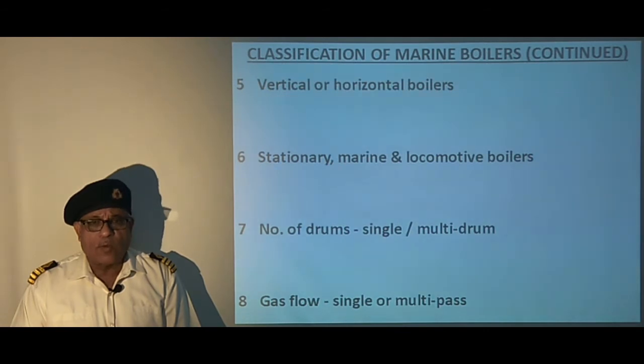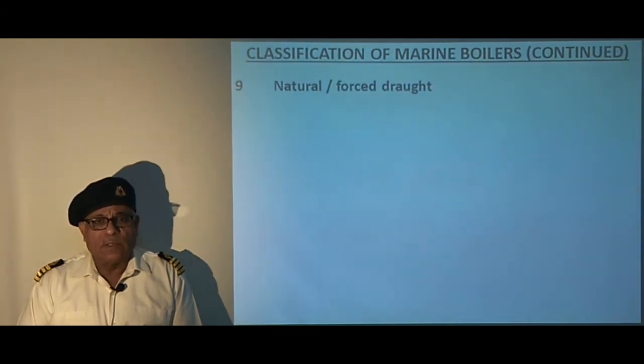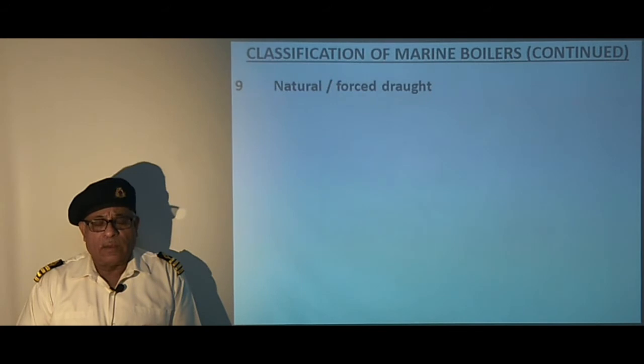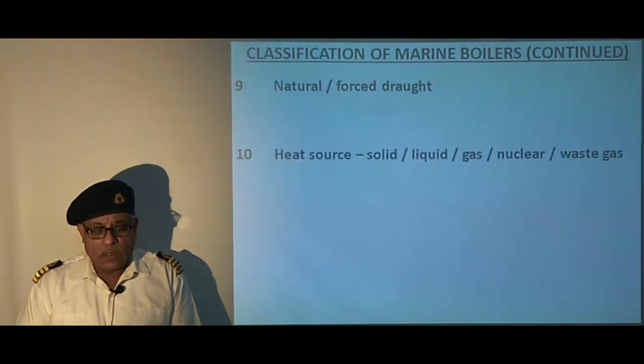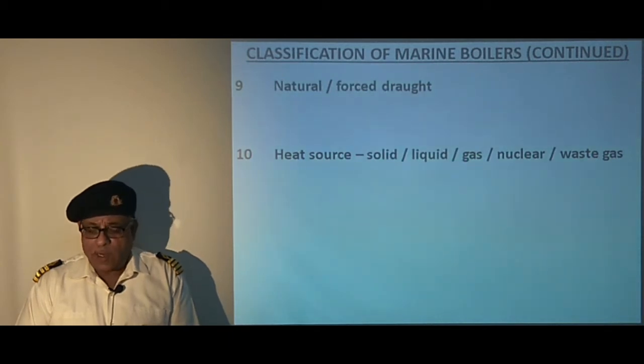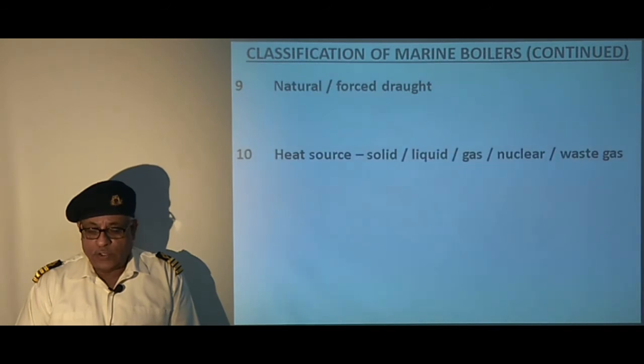Now, natural or forced draft: combustion air in most boilers is supplied with a forced draft fan, although very small boilers may have a natural draft, and very large boilers may have both forced and induced draft fans. As per the heat source, large boilers in power plants use solid fuel which is pulverized coal, while most marine boilers use liquid fuel, although natural gas is gaining popularity due to strict emission rules.